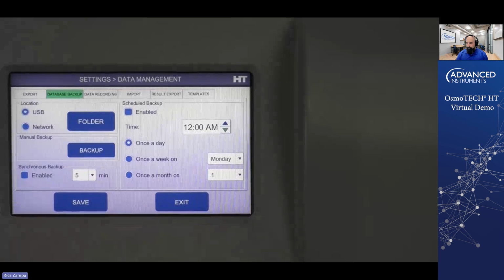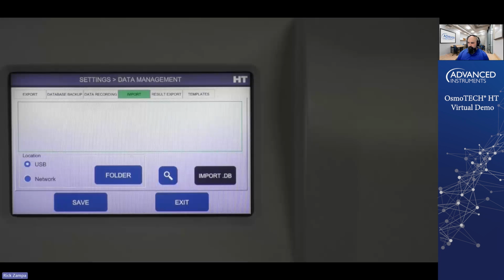And it's really a matter of your IT department's preferences as to how they want these backup files stored so that they can use them at a later date if needed. As I said, the backup files also store the configuration files, so if there was ever a catastrophic failure, you could take your last backup file, go to the import functionality, and import it back to the instrument and be up and running from that point in time.